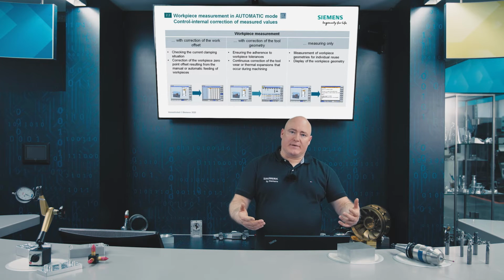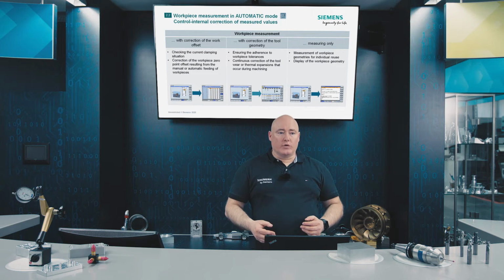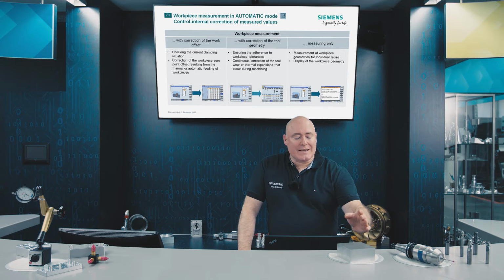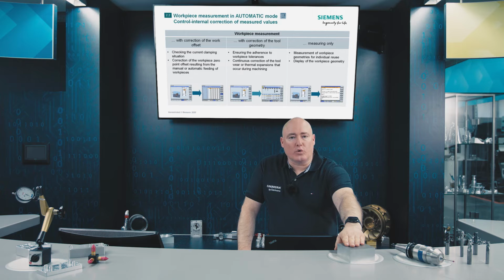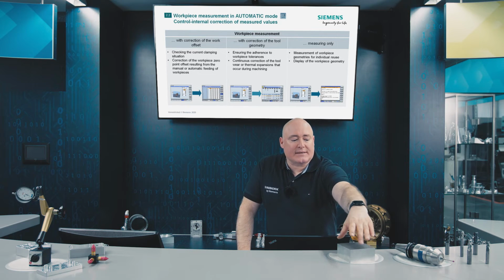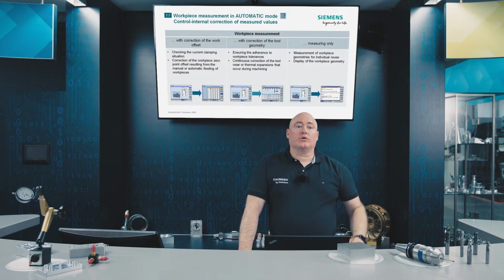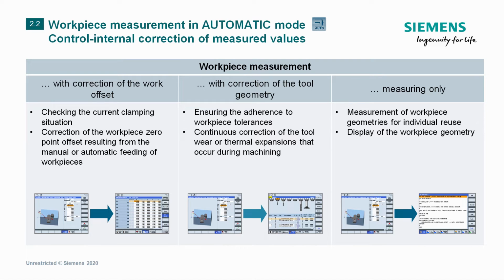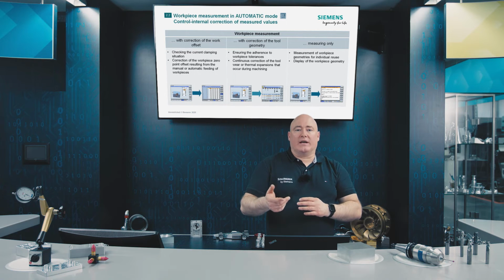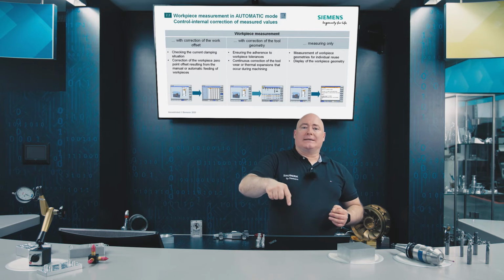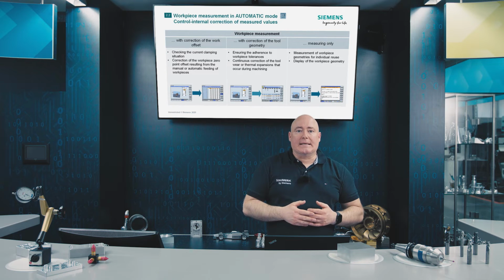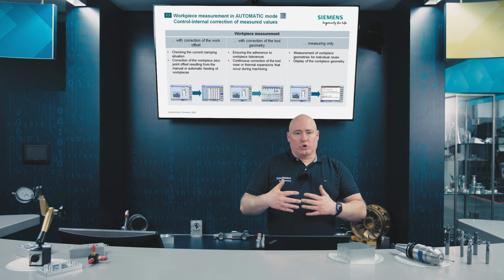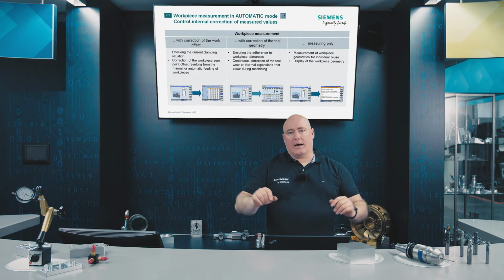In automatic mode, in other words during process measuring, 3 functions are available for measuring a workpiece. One of them is the compensation of the workpiece's work offset. This means, for example, if blanks are fed automatically into the cutting zone, a previous measurement makes sure that the blank is really in its specified position. The second function is the correction of the tool geometry. A good example of this is milling a pocket. When the measuring cycle is activated automatically, the probe measures whether the pocket matches the preset contour or dimensions. If it's too small, the workpiece is made smaller by the respective value, for example. Machining restarts to get the pocket to the required dimensions and ensure dimensional accuracy. The third function is measuring, simple, straightforward measuring, where a measuring log can be output and stored as required by the operator.